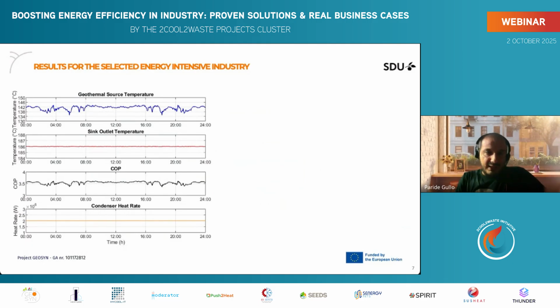Looking at the results, we have 4 graphs, each with time over the 24 hours on the x-axis. At the top is the temperature of the geothermal well, using real field measurement values. What we're most interested in is the sink outlet temperature, since we want to provide the dairy facility with 186 degrees Celsius, and we achieved this target throughout the whole 24 hours. We also wanted a COP above 3, and the COP stays above 3 the whole day. Finally, we wanted to provide 2 megawatts, and as shown at the bottom, we achieve this 2 megawatts over the full 24 hours.